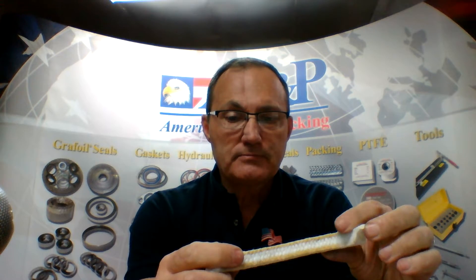It did evolve, and your most common packings that use Kevlar in centrifugal pump applications would utilize another packing in the core and only use the aramid fiber on the corners. So it acts as an anti-extrusion device as well as a wiper. The core is generally either a GFO — which is a blend of flexible graphite and PTFE — straight PTFE, or more often a PTFE-coated acrylic yarn used in the center.